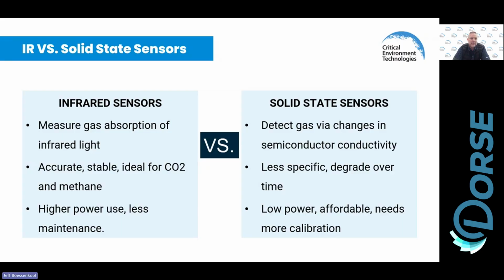So all sensors have a shelf life. Of course, the solid state sensors more so than the infrareds. But if you think about this sensor, I mentioned earlier, it's like an electrolyte inside. If we keep this sensor on the shelf for 10 to 12 months, the insides will dry out a little bit to the point where you will not be able to calibrate that sensor, right? So by virtue of this sensor being plugged in to the unit, it heats up and it will extend the life of the system.